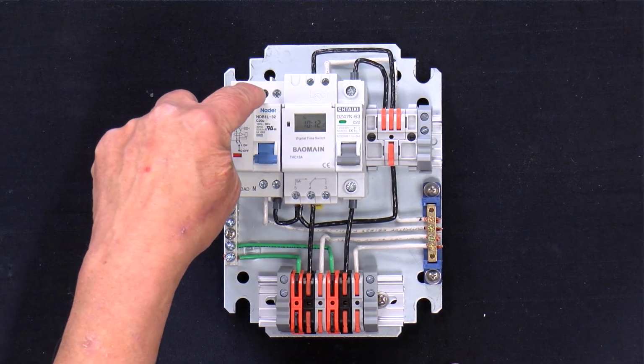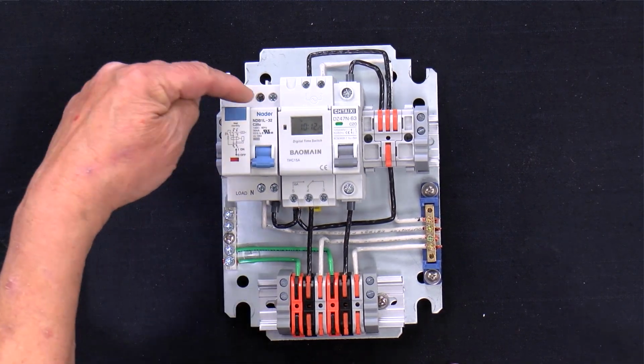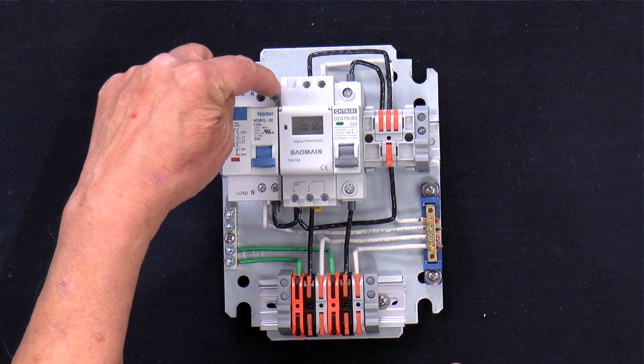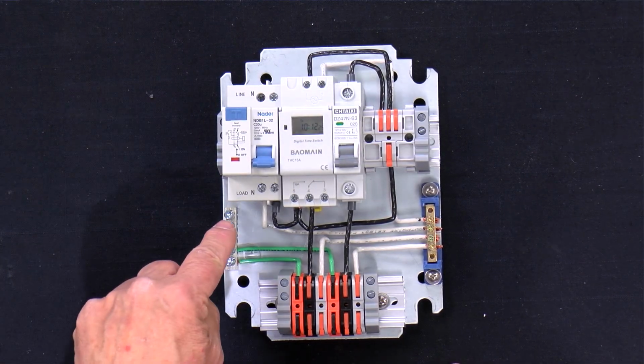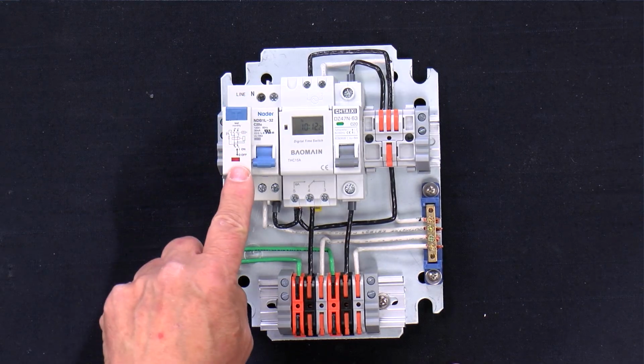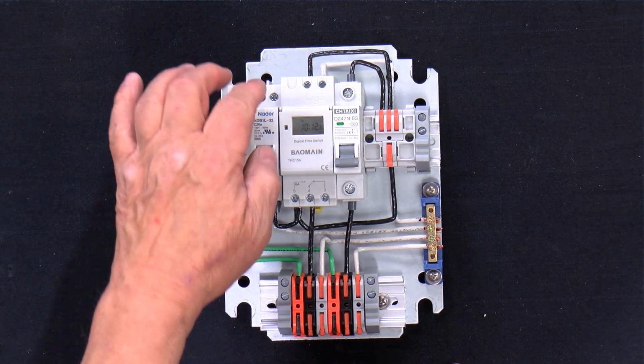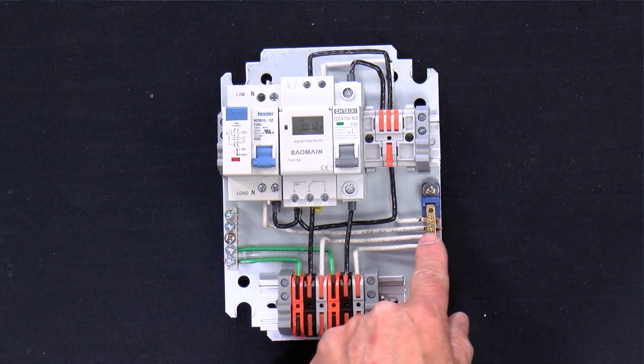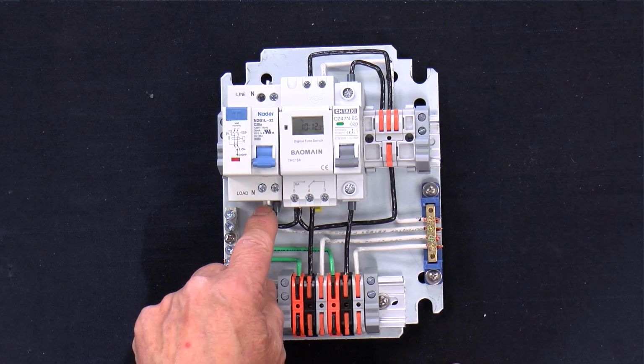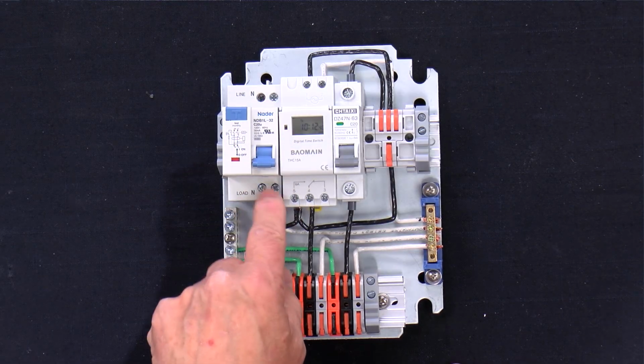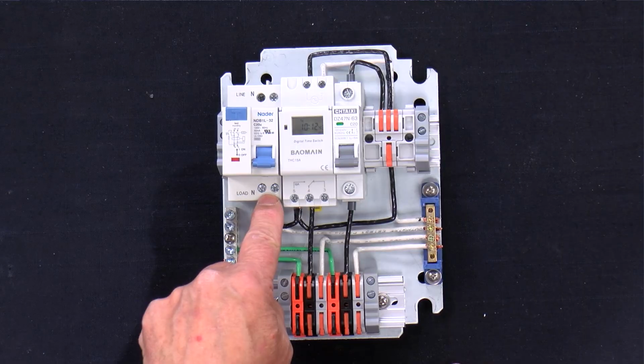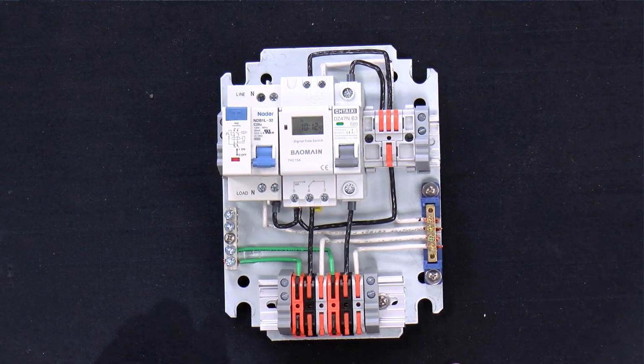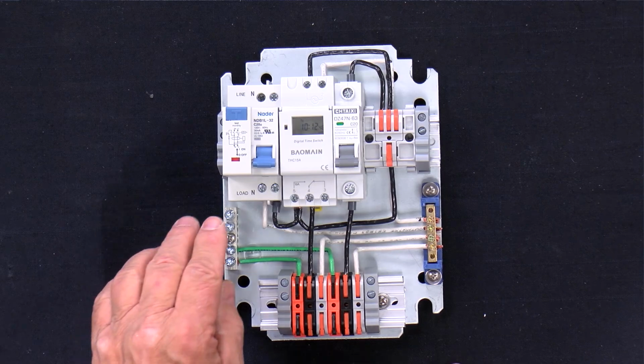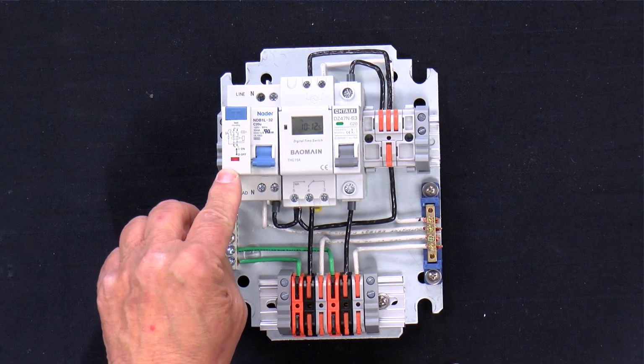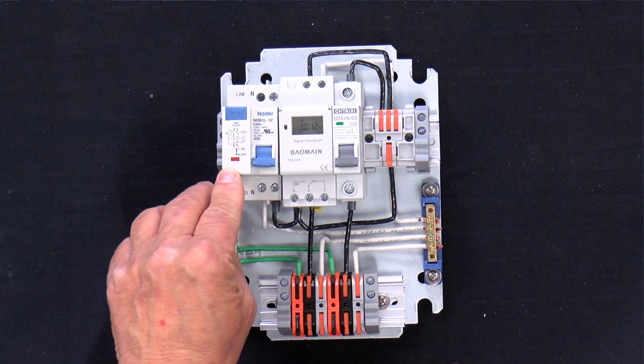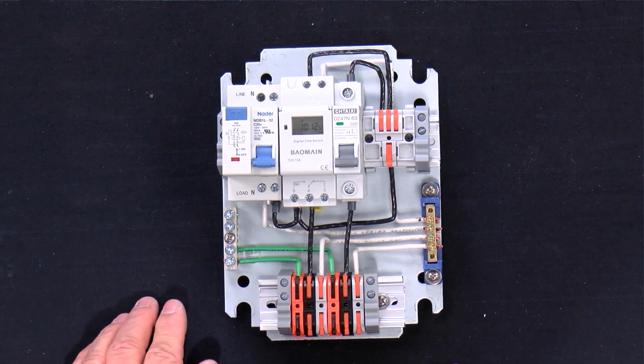Power comes into the GFCI breaker at the top. There's a neutral line and a power line, and of course a ground. GFCI breakers are unique in that the neutral line flows directly through, as you can see over here. So really the only thing that's switched is the line, and on the other side is the load. This particular GFCI breaker is for a normal spa system, one that does not have an automatic dosing system in it.